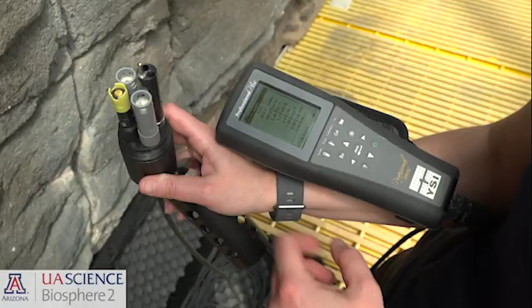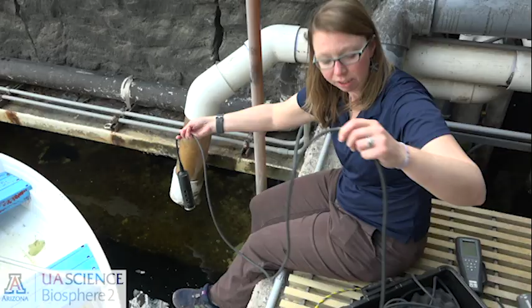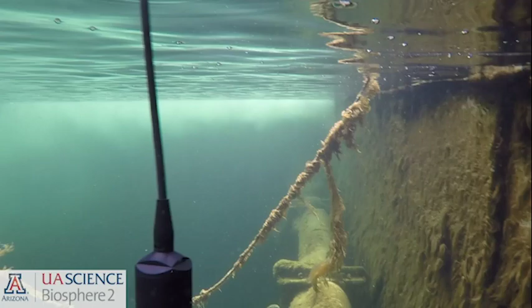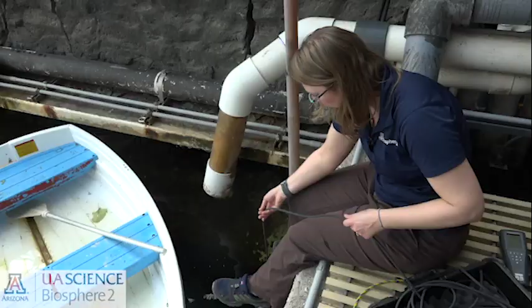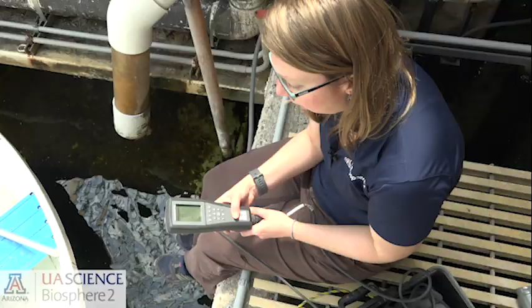And you can see it trying to log the data of the air here. One of the nice things about the Professional Plus series that we have here is it actually tells you when the value stabilized. So you'll see a lot of things blinking because it's not sure what the value of conductivity of the air is, which is probably okay, right? This 30-meter long cable has markings every meter, so we can get a profile with depth. I'm going to slowly lower this in until that black marking is at the water column, right there. Turn our instrument on and wait for it to stabilize.